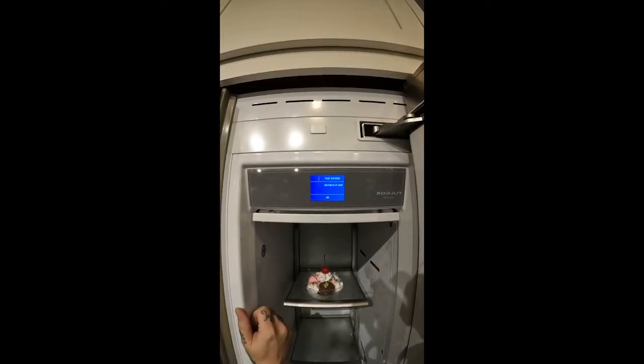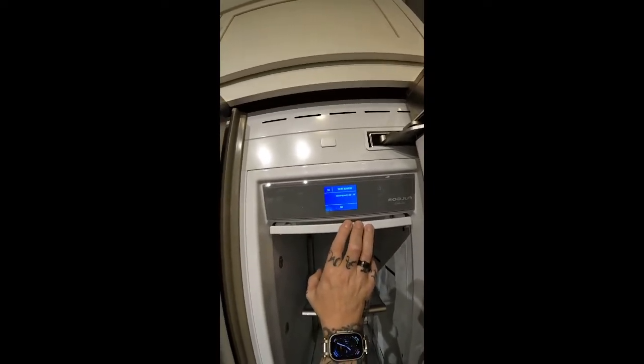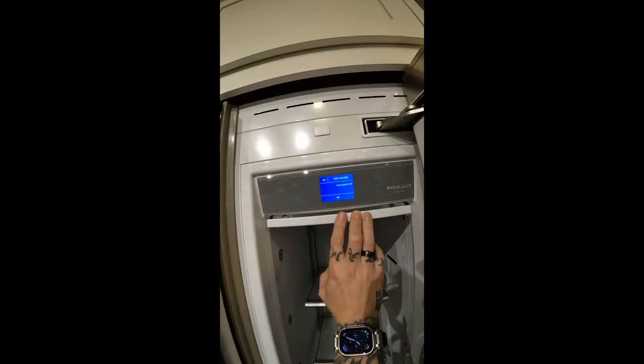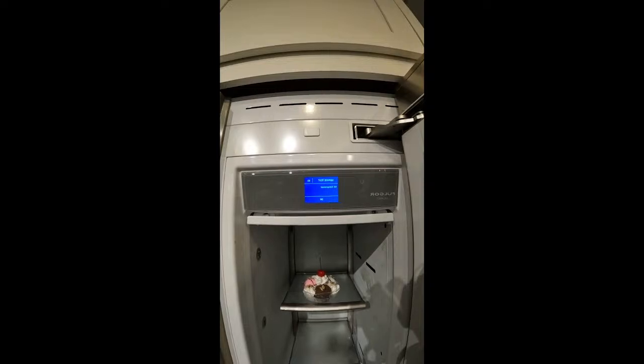The first two parts of this test are your compressors. Since this is a freezer column, we only have one compressor that's going to run. V1, V2, that's your fresh food compressor that will not run on this model. It is a column. V3 compressor. So if you wanted to diagnose this compressor, customer complained no cool on this machine, you can take your meter and put it into the frequency wire, your DC voltage wire, onto your inverter and check for hertz, for frequency at this point. And then you can watch your meter reading frequency rise because it's a VCC compressor. And the higher it goes, the faster the compressor is going to run.